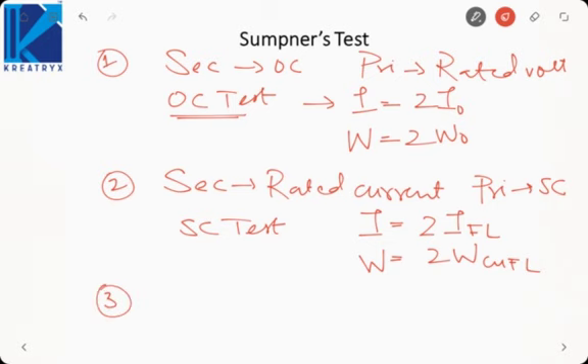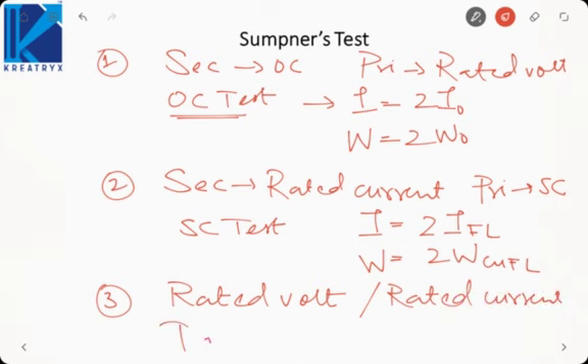In the third step, we connect both the sources. None of the windings will be open circuited or short circuited. On both the windings, we apply rated voltage and rated current, and we record the temperature rise. This gives us an idea of how much cooling is required in such a machine, and whether the temperature rise under working condition can be hazardous to the machine. Can it damage the windings or the core of the transformer? So those are the steps in Sumpner's test. We first conduct the open circuit test and then the short circuit test. These two tests help in finding the efficiency of the machine. In the last test, we connect both the sources simultaneously to estimate the temperature rise in the machine. That is how Sumpner's test is conducted.